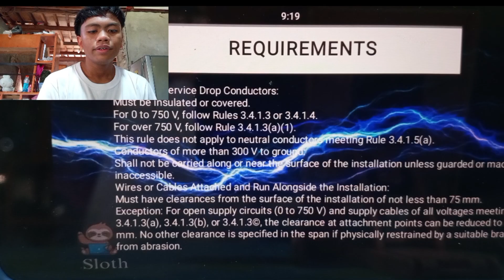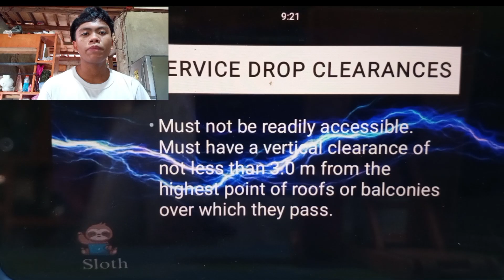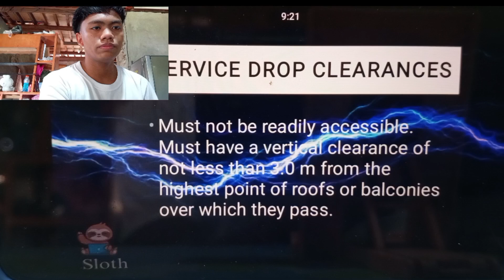These are also the mandatory requirements for installations: voltage limits, surface proximity, and minimum clearances from the installation surface. Service drop clearances, where not readily accessible, must have a vertical clearance of not less than 3 meters from the highest point of the roof or balcony over which they pass. This is the standard so that anyone can pass easily, for example while using a vehicle, and for other installations.